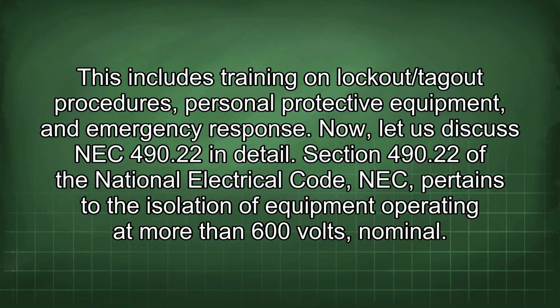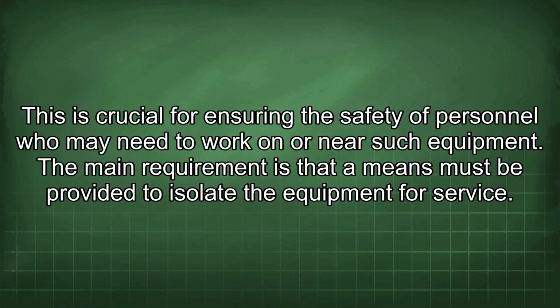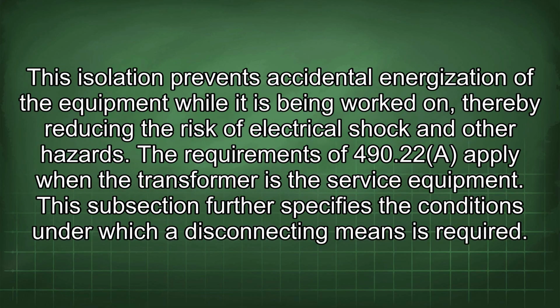than 600 volts nominal. This is crucial for ensuring the safety of personnel who may need to work on or near such equipment. The main requirement is that a means must be provided to isolate the equipment for service. This isolation prevents accidental energization of the equipment while it is being worked on, thereby reducing the risk of electrical shock and other hazards. The requirements of 490.22 apply when the transformer is the service equipment. This subsection further specifies the conditions under which a disconnecting means is required.